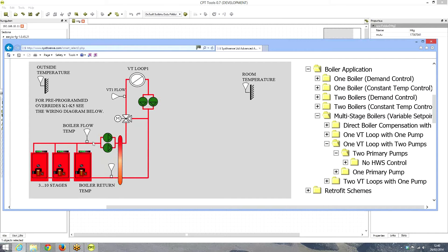The boiler control will measure the boiler flow temperature and modulate the boilers according to requirement — when temperature drops, we modulate boiler one, two, and three. We also want to rotate the lead boiler: in the first week boiler one is the lead, then boiler two, then boiler three. This reduces wear and tear. In many BMS systems this is complicated, but with our SixSense application kits it is really simple.